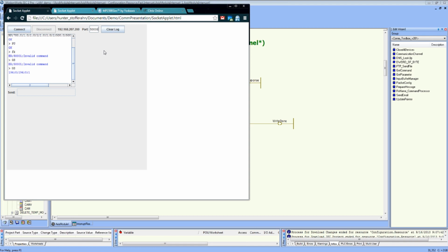Yeah, there's a question. Go ahead, Hunter. Yeah, it would work exactly the same coming from a Rockwell. Can you read the question? Oh yeah, sure. The question is, would these techniques be used if you're using a Rockwell controller to send ASCII commands to the Yaskawa controller? Basically, it would work exactly the same. Specify the Yaskawa controller IP address and port number to send ASCII commands, and the setup should be exactly the same as a Visual Basic or Visual Studio code.